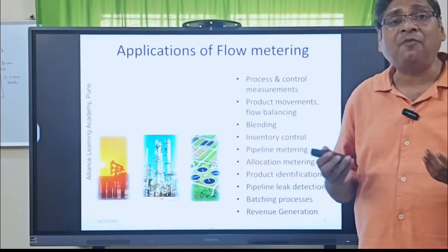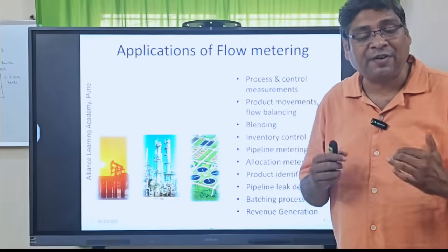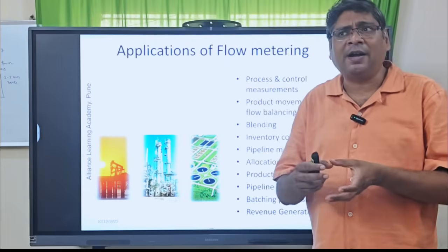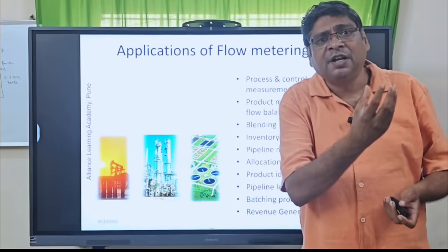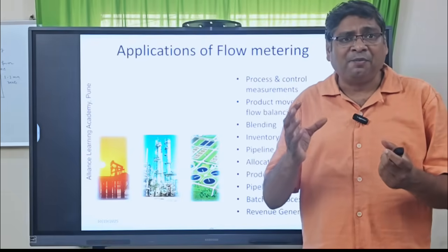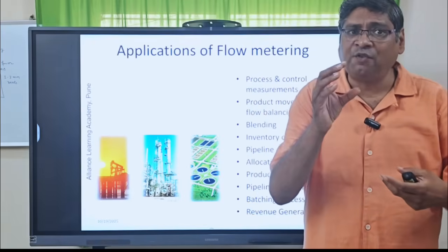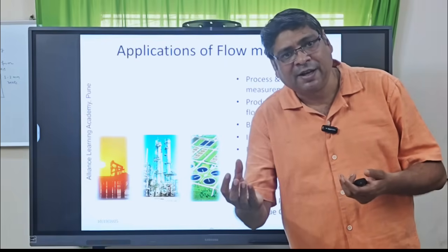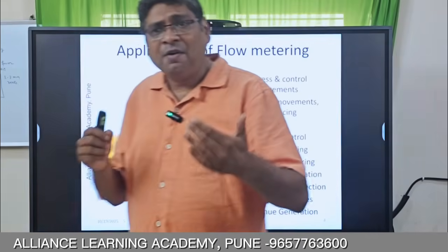Allocation metering is very important nowadays when we talk about energy efficiency and productivity. Depending on the process, we calculate how much fluid, gas, or steam is required for a particular process. In residential societies, depending on population, they calculate how many liters of water are required. At the inlet, there is a flow meter, a small RTU or PLC, and a control valve. Once sufficient water has flowed as per the calculation, the valve closes. This is called allocation metering.